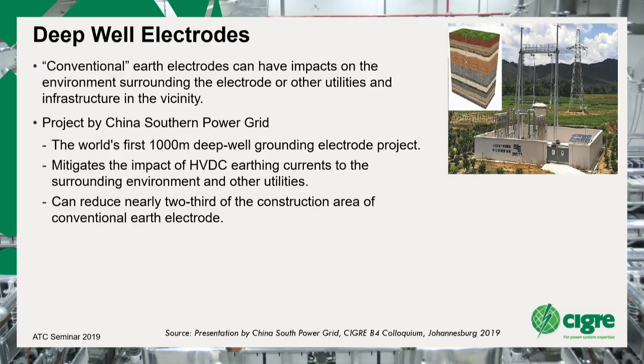Deep well electrodes, very quickly, China have put in these big 1,000 metre deep electrodes. The thing about earth return is that if you can place an electrode somewhere where you can force the current as deep as you can into the ground, then it won't have any impact on anything on the surface, whether it's a fence, a pipeline, or the environment.